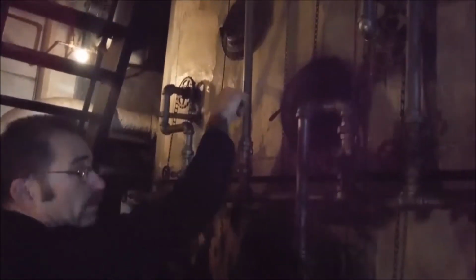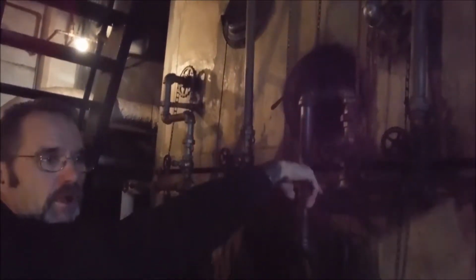Still, it can be a bad day when those things happen. So Chris, you see these chains? I'll bet I know what those are, but correct me if I'm wrong. When you're burning your boiler, you get soot on the outside of the tubes, and that soot's a great insulator, and it'll slow down your heat transfer. So these are probably steam pipes that go into nozzles called soot blowers, and every so often you open these valves and pull these chains, rotate that soot blower head 360, and steam blowing in on the fire side of the boiler blows the soot off the tubes.